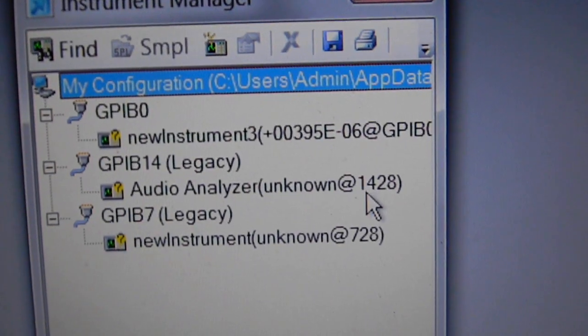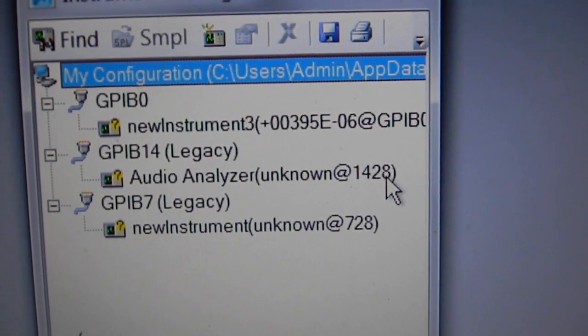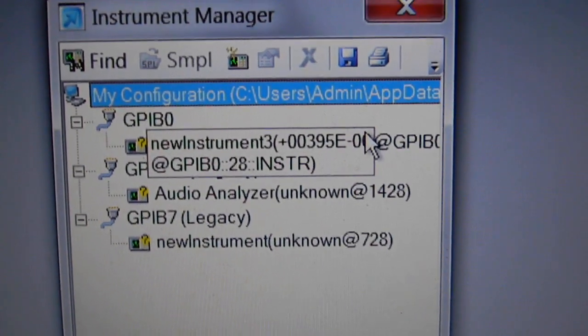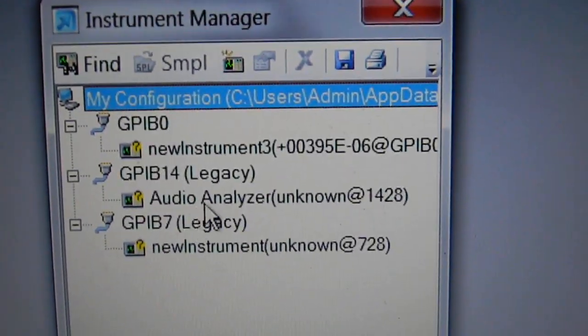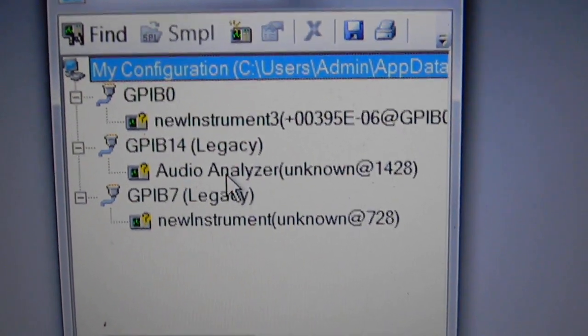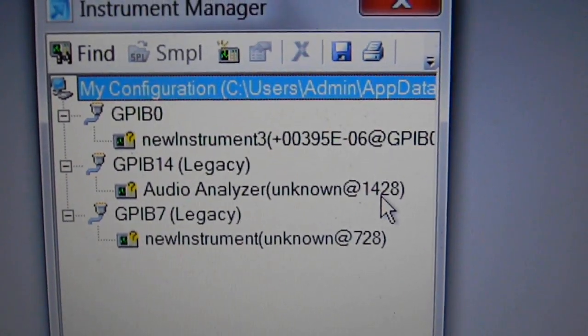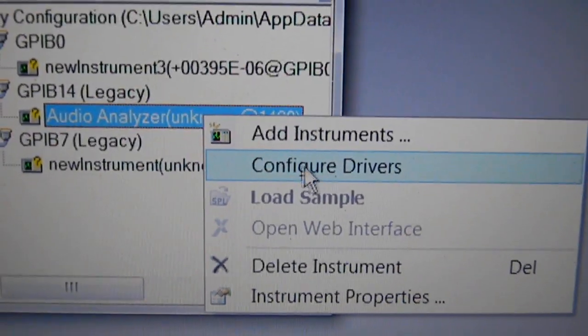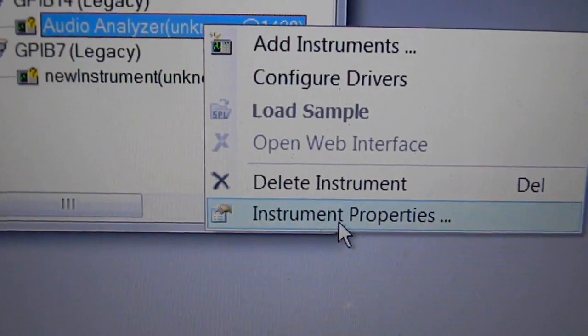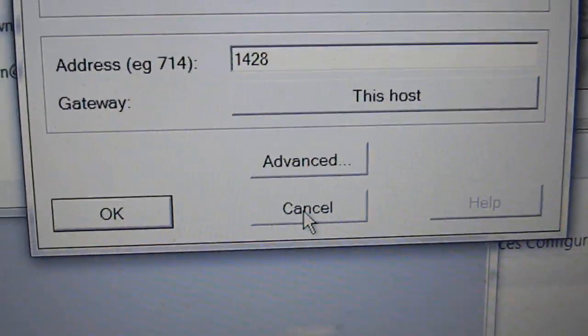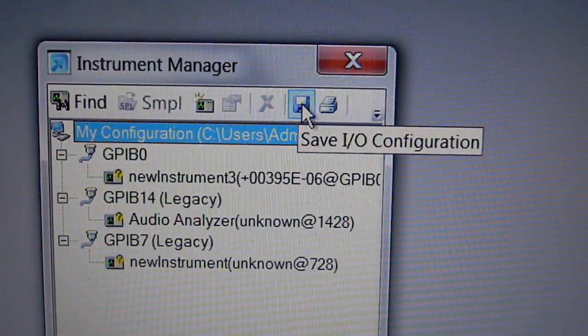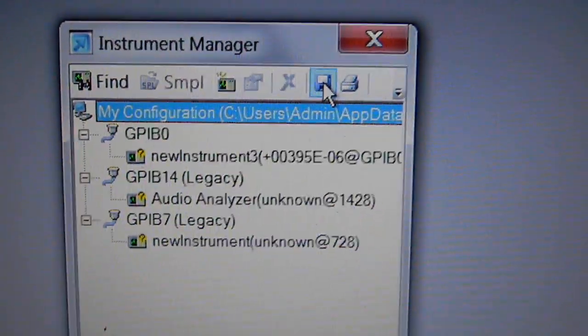If you read his documentation completely, his is looking for something at address 1428, which is right there. This one up here is probably the controller itself, the GPIB0 controller. This is probably a device under the controller. I renamed this one because this one had the address that his software was looking for. Right click, you just say instrument properties. Right there is where I renamed it Audio Analyzer. And then in the end, the dumbest thing that bit me for a long time is you've got to go right up here to this little guy that says Save IO Configuration. Don't forget to click on that because if you don't click on that and save it, it doesn't get saved.